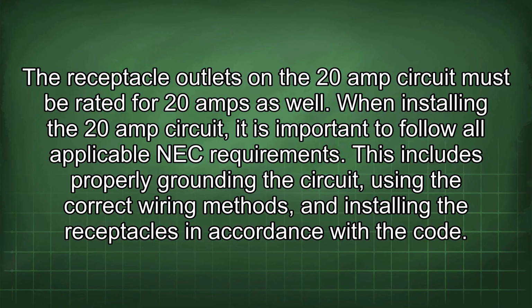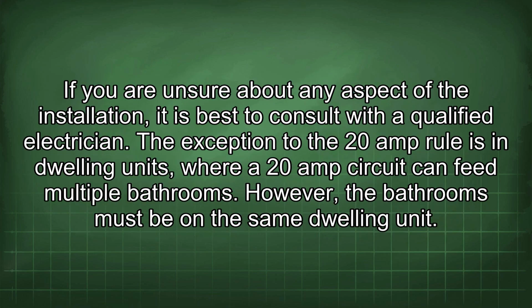When installing the 20-amp circuit, it is important to follow all applicable NEC requirements. This includes properly grounding the circuit, using the correct wiring methods, and installing the receptacles in accordance with the code. If you are unsure about any aspect of the installation, it is best to consult with a qualified electrician. The exception to the 20-amp rule is in dwelling units, where a 20-amp circuit can feed multiple bathrooms. However, the bathrooms must be in the same dwelling unit.